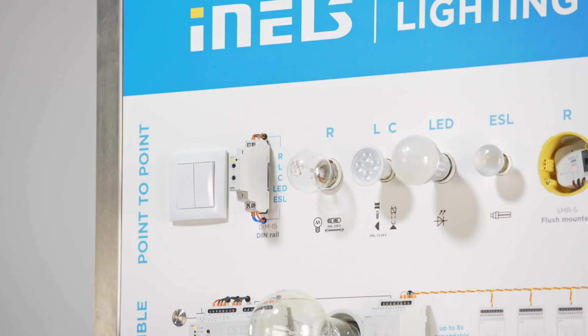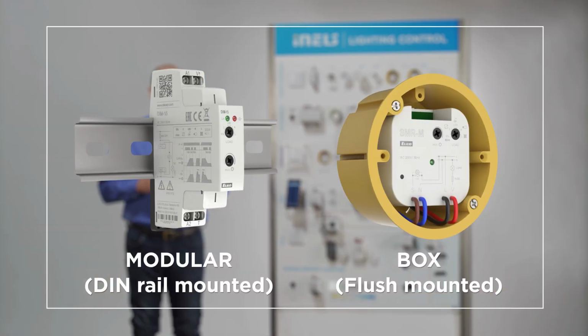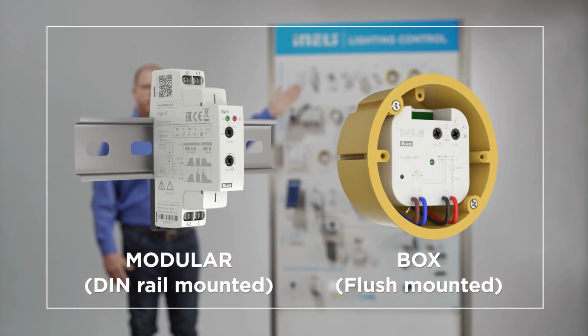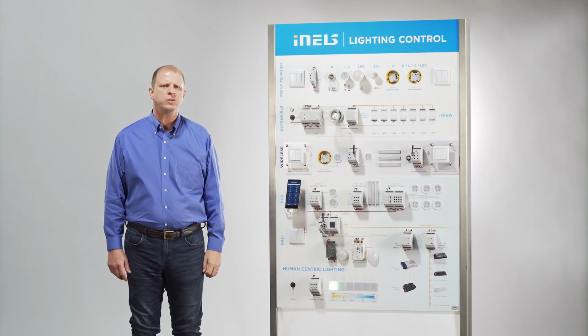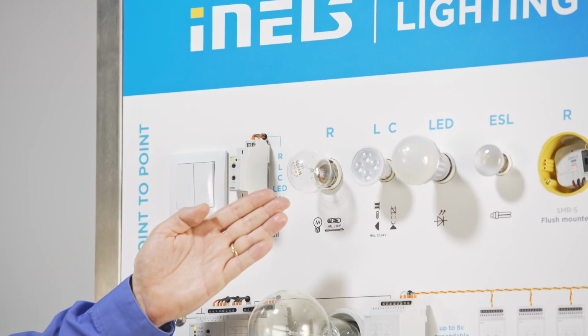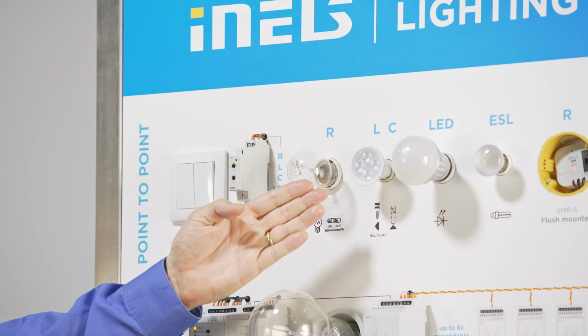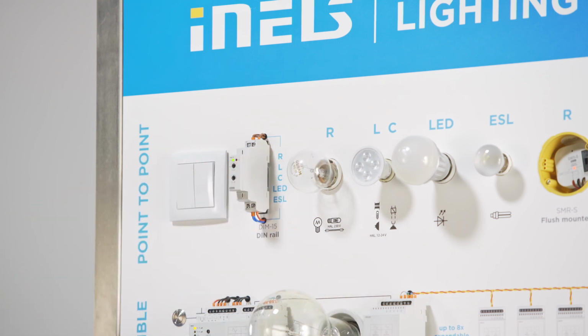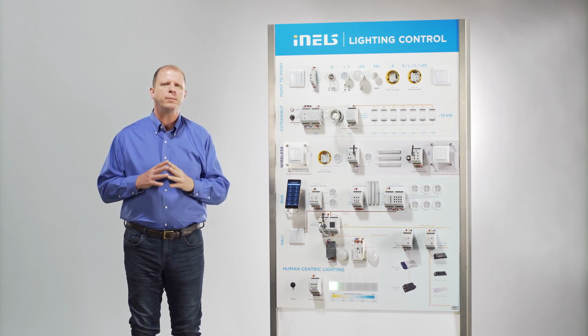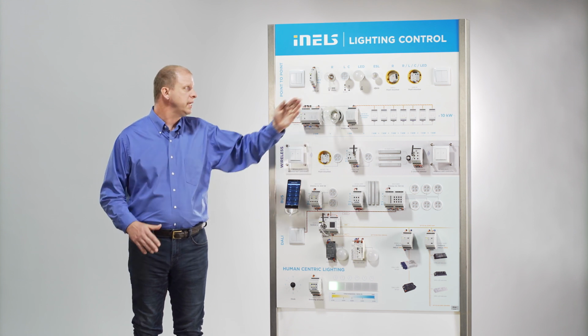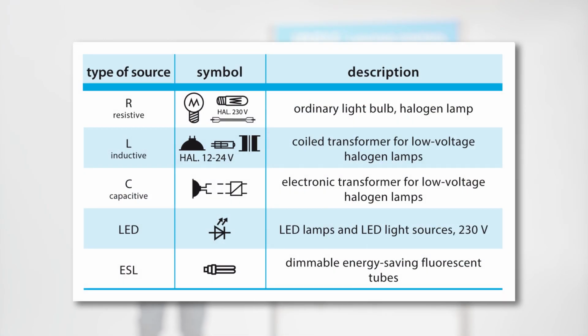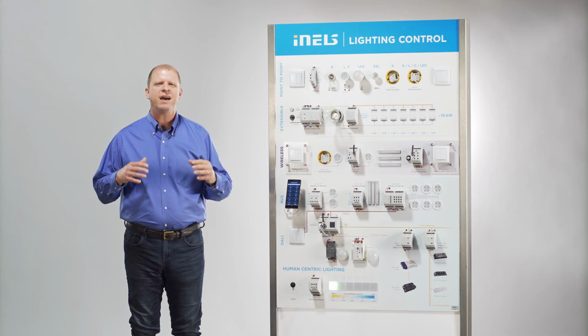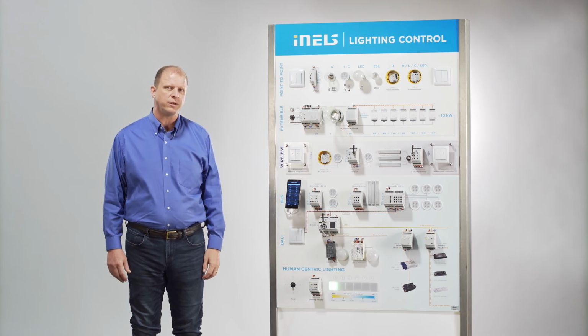The basis of the whole solution is a dimming actuator in a boxed or modular design on a DIN rail, capable of controlling various loads. It can be resistive, inductive, or capacitive. All actuators are also able to control energy-saving fluorescent lamps and LED lights up to 230 volts. And they have a memory in the event of a power failure.